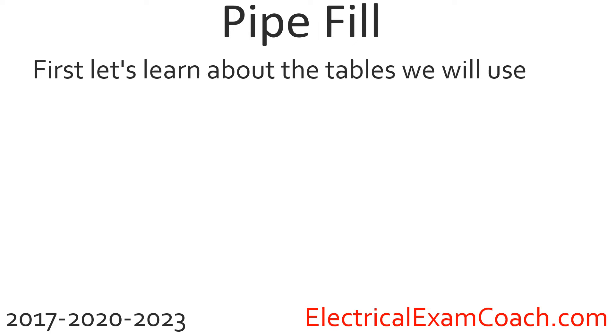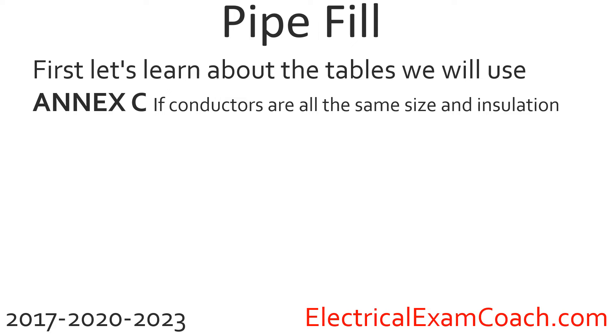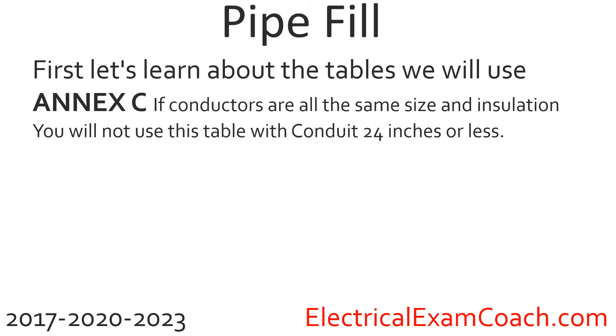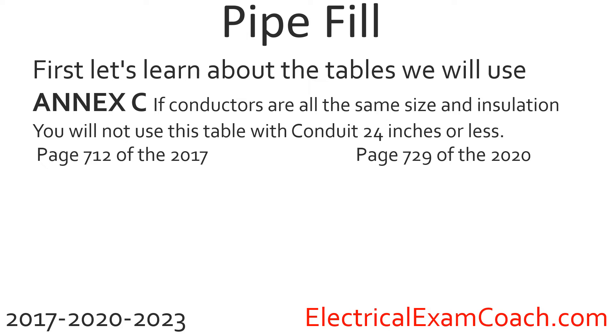Let's learn about the table we'll use when they are all the same size. We're going to use Annex C — if you've tabbed your codebook, you have an Annex C tab. If the conductors are all the same size and insulation type, we get to use a cheat sheet in Annex C. It's one of my favorite tables in the codebook. You will not use this table if the conduit is 24 inches or less — the codebook calls those nipples. For those, use the method in lesson 7.2. You can head to page 712 of the 2017 edition, page 729 of the 2020 edition. This video is 2023 compatible — find your page number for Annex C and follow along.